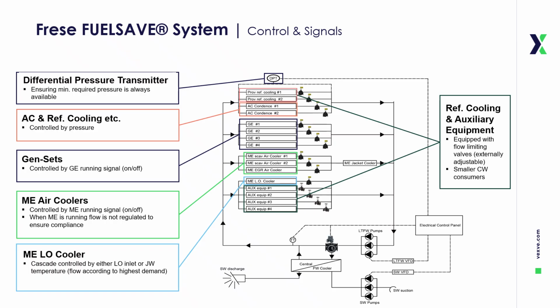This closed-loop design guarantees that performance remains stable under all operating conditions, while minimizing pump energy consumption and securing maximum fuel savings. In practice, the Frese FuelSave transforms flow control from a static setup into a fully automated, responsive system, delivering both operational reliability and measurable efficiency gains.